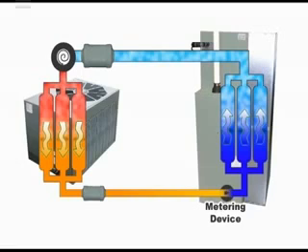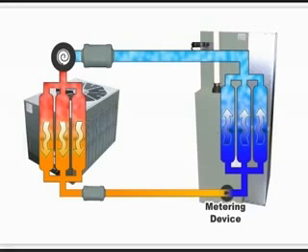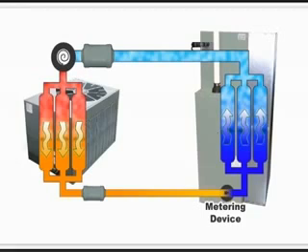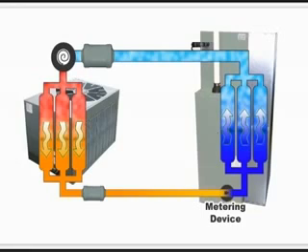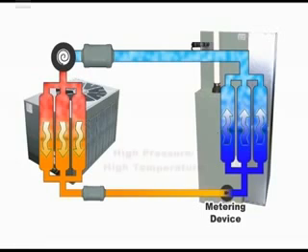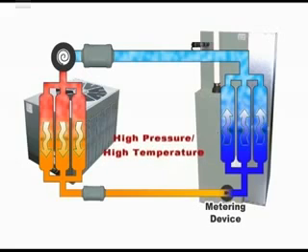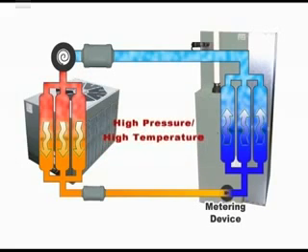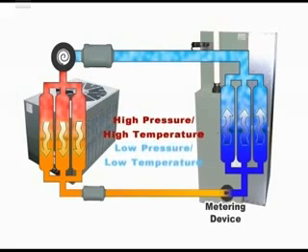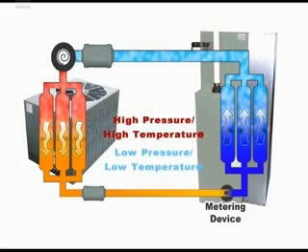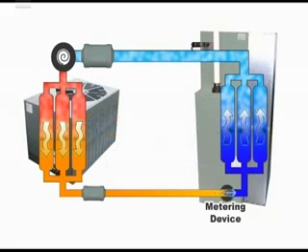To achieve this condition, we use the refrigerant's properties of high pressure/high temperature and low pressure/low temperature. By forcing the refrigerant through the metering device, a drop in pressure occurs, resulting in a significant lowering of the temperature of the refrigerant.